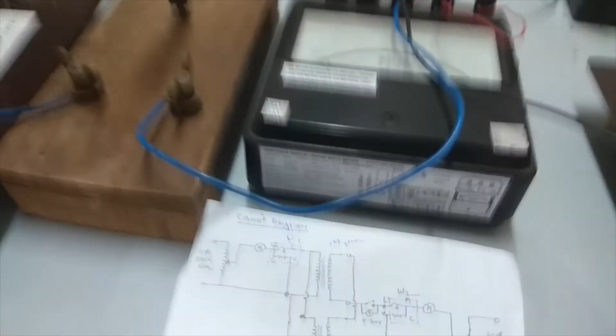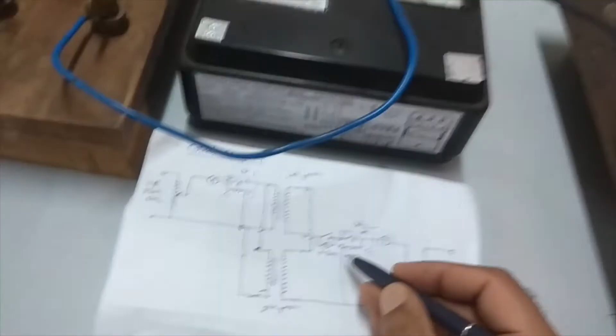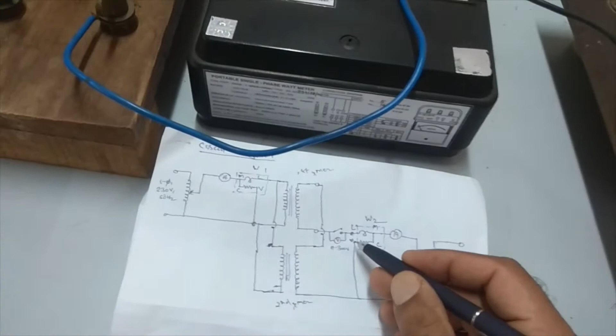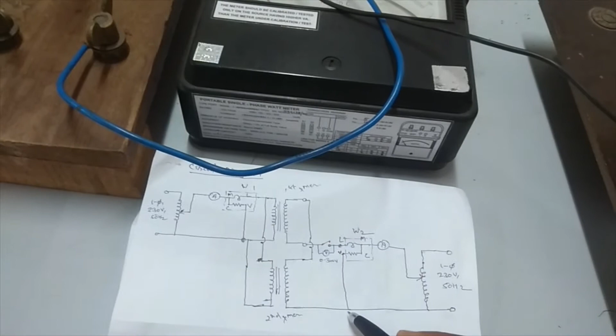We can see this is the second terminal of the first transformer secondary, that is connected to, you can see this wire, which is going to connect the second terminal of the second transformer secondary. And the one terminal which has to be connected to the supply is connected here, and the V terminal is pending. So V is connected to the second terminal of the supply, or it can be connected to this terminal of the transformer. Okay, so we have connected it to the supply.